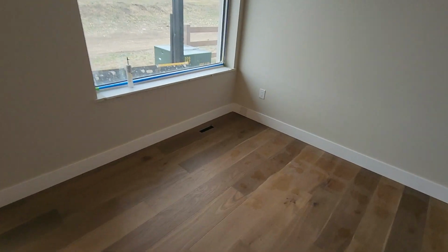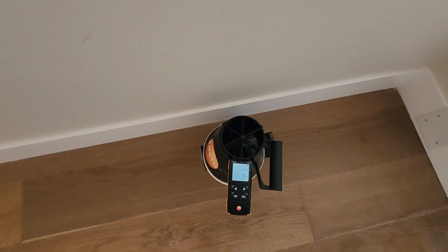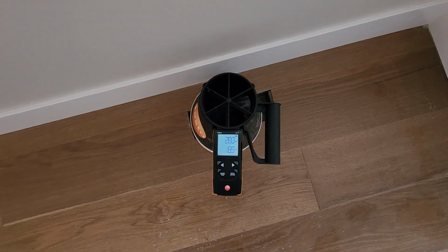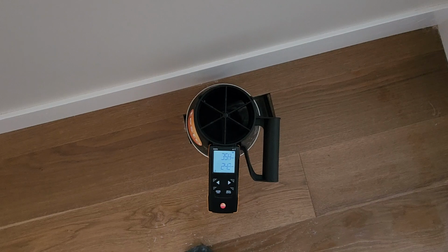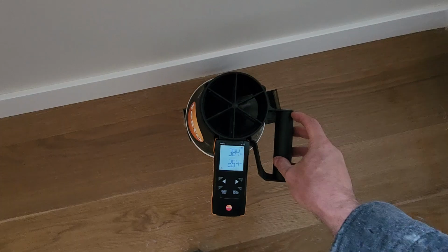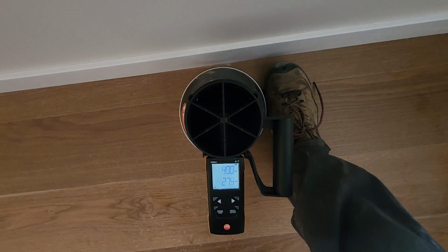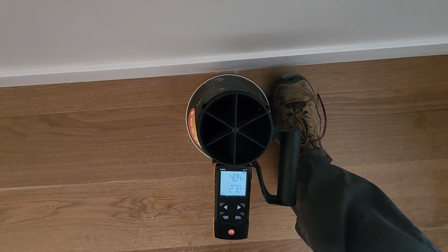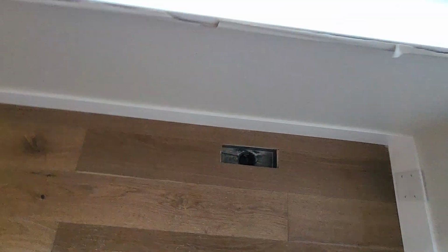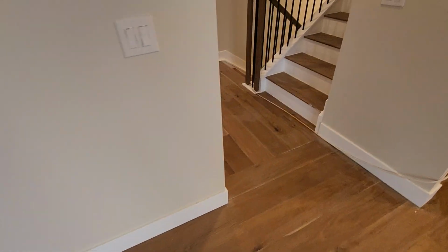For instance, why don't we go over to this corner over here? This is supply air for the living room. This is fresh air for the living room. So if you're sitting right here, you're going to get air coming out. Right now it's showing about 25 CFM, 26 CFM, but it's actually more than that because I should use the larger piece, but we're really looking at about 27 CFM or so for this particular room, or for that corner. I have another 20 CFM or so for that room.